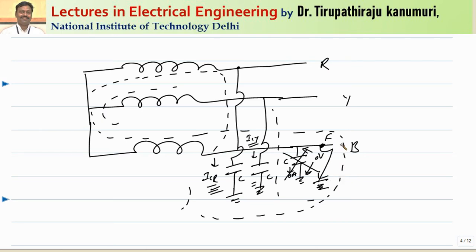The current passing through the R phase capacitance and the Y phase capacitance will close through the B phase — that means through this fault. The fault current can pass and the closed circuit is possible for this winding. Because when this winding is connected to ground and there is no grounded neutral, the only option the current can close is through these capacitive currents. Now, the capacitor of the R phase is connected between R phase and ground, and that ground is now connected to B phase. So the current ICR will be due to the voltage between R phase and B phase — that is Vrb. Similarly, the current through CY will be due to the voltage between Y phase and B phase — Vyb.